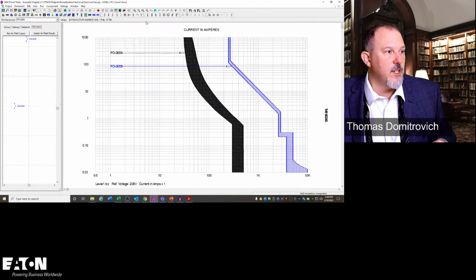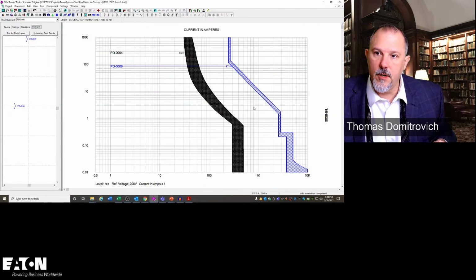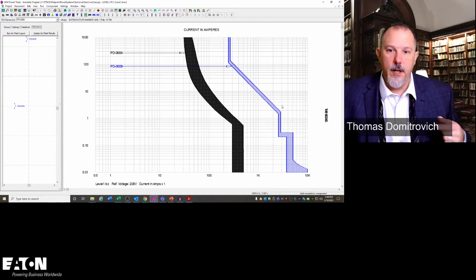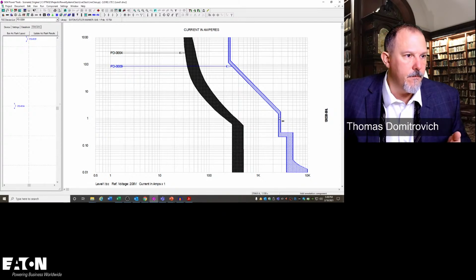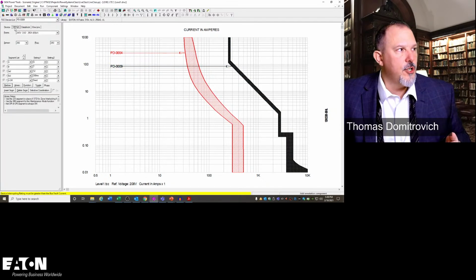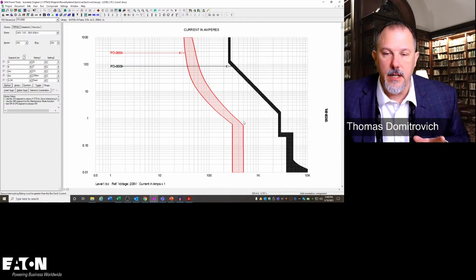And I say new. Okay, now I've just plotted these two trip curves, which is breaker 1. That's the BAB, this one here. And then I have breaker 2. The upstream breaker is a KD breaker, a 250 amp KD breaker. And I have obviously clear separation.